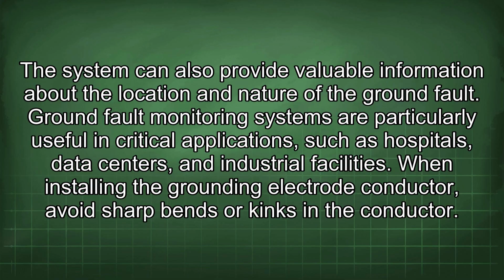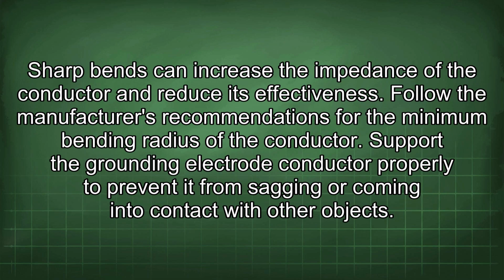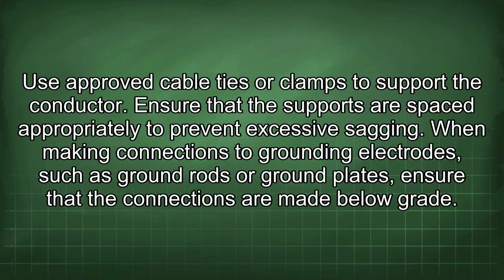When installing the grounding electrode conductor, avoid sharp bends or kinks in the conductor. Sharp bends can increase the impedance of the conductor and reduce its effectiveness. Follow the manufacturer's recommendations for the minimum bending radius of the conductor. Support the grounding electrode conductor properly to prevent it from sagging or coming into contact with other objects. Use approved cable ties or clamps to support the conductor. Ensure that the supports are spaced appropriately to prevent excessive sagging.